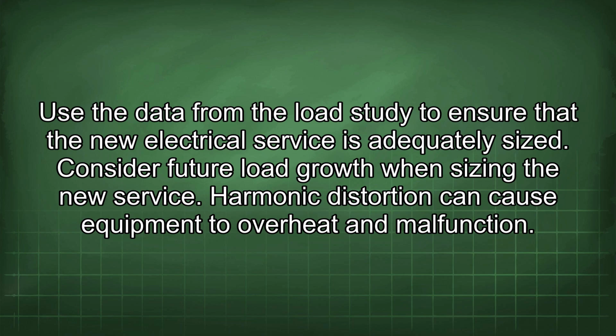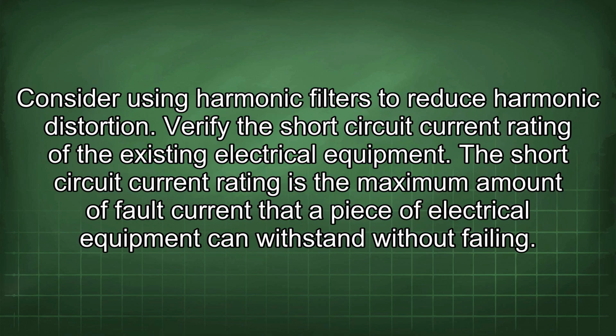Harmonic distortion can cause equipment to overheat and malfunction. Consider using harmonic filters to reduce harmonic distortion. Verify the short-circuit current rating of the existing electrical equipment. The short-circuit current rating is the maximum amount of fault current that a piece of electrical equipment can withstand without failing.